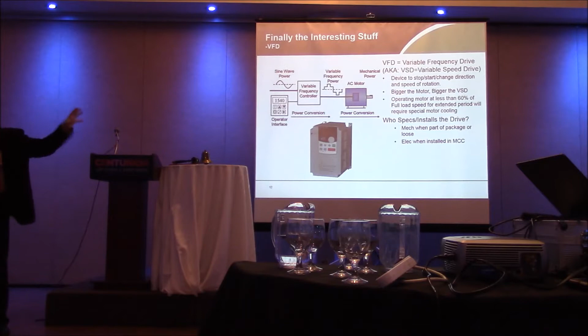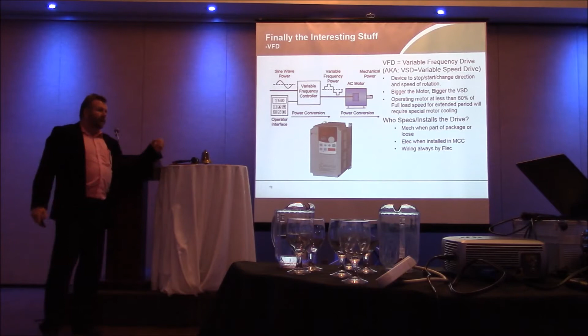A lot of the time I've run into situations where a MCC manufacturer, Square D, the HVAC equipment manufacturer wants to use a Danfoss drive or wants to use an ABB drive or an Eaton drive. But Square D has got the MCC, so you've got a Square D MCC that somebody's putting an Eaton drive inside of, and Square D and Eaton don't like each other because they chase each other's business. And it just never seems to end well. Wiring should be by electrical, and electrical should be talking about that. And in a second, I'm going to show you how electrical should be talking about that.